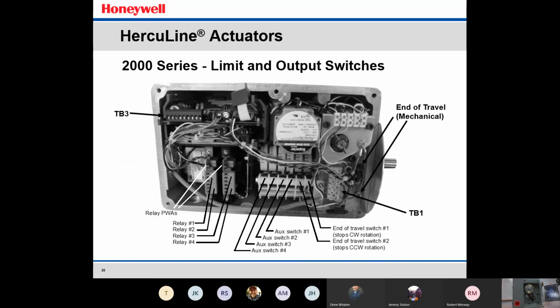If we were to remove the top lid on the Herculine 2000 actuator, this is what you would see inside the actuator. Over on the far right-hand side, this is where you would hook up your power, also 4 to 20 milliamp. You have your end of travel limit switches and auxiliary switches below that. You'll have your programmable relays to the left, along with the power supply to the actuator. And then up at terminal block 3 is where you have your communications and some other connections up there as well. But you can see that if you remove the top lid, everything is very easily accessible. And every single lid has on the inside of it a map of the wiring instructions as well.